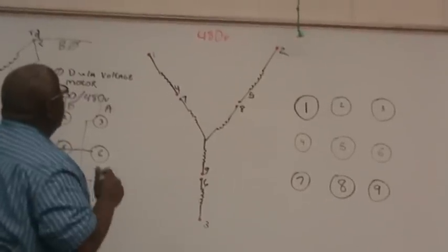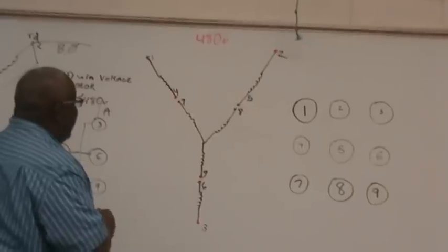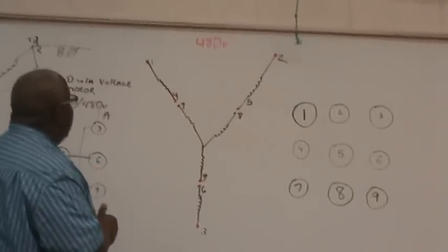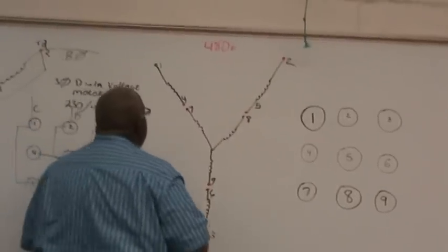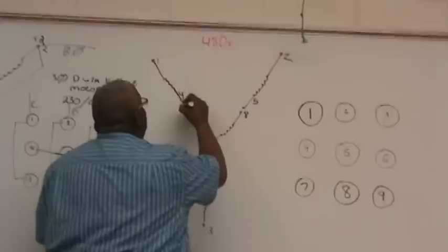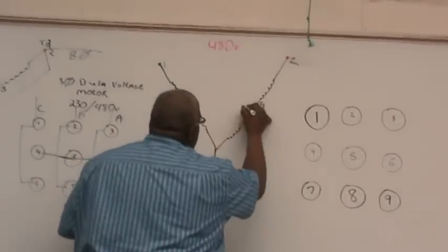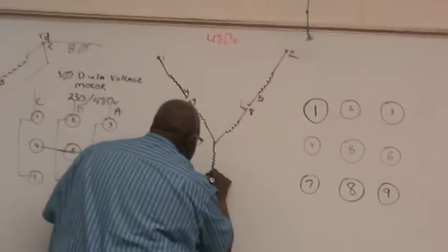Now, for high voltage, it's really easy for electricians to remember versus doing it in low voltage. When I say tie in series, I really do mean tie in series. Tie four to seven, five to eight, and six to nine.